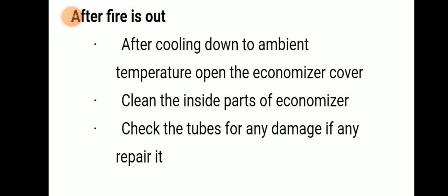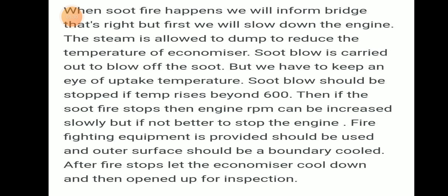After the fire is totally out, cool down to ambient temperature, then open the economizer cover. Clean the inside part of the economizer and check the tubes for any leakage or damage. If any damage is found, repair it.